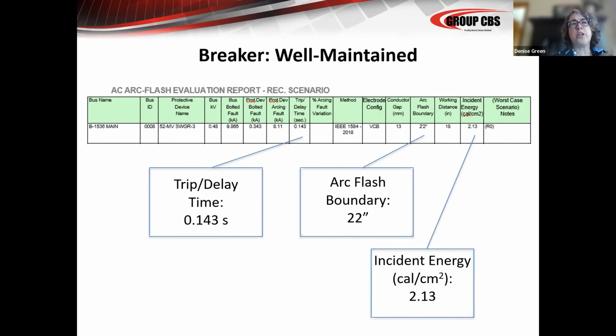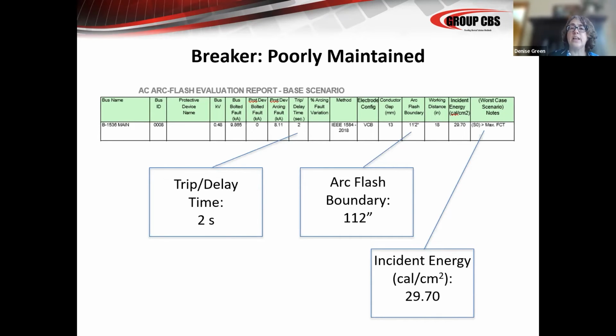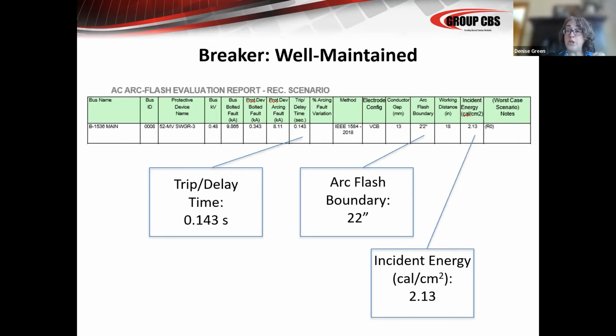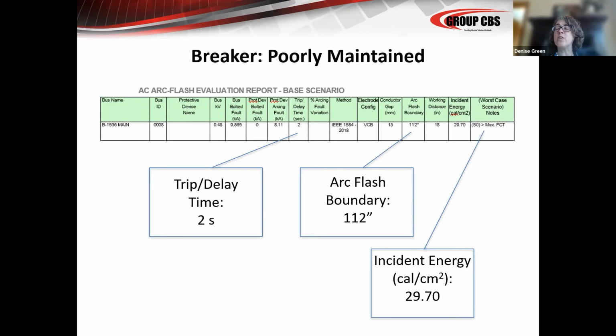It's going to tell them to have a face shield on, safety glasses, earplugs, the proper shirt, usually an 8 calorie shirt because that's what you should wear. And the technician or the electrician thinks that they are completely protected. Okay. This exact breaker, same main breaker, if that trip delay time extends to 2 seconds instead of 0.143 seconds, you now have an arc flash boundary of 112 inches instead of 22. And your incident energy is now 29 calories, almost 30 calories.